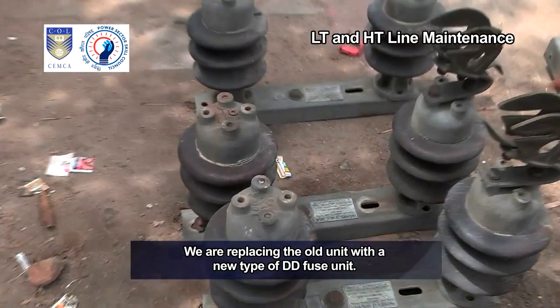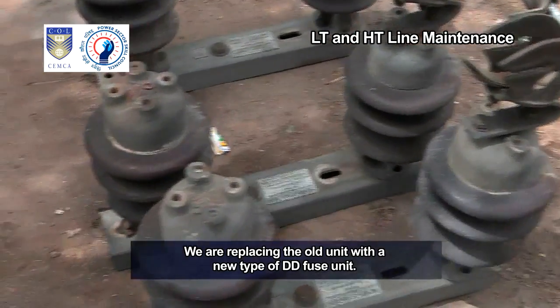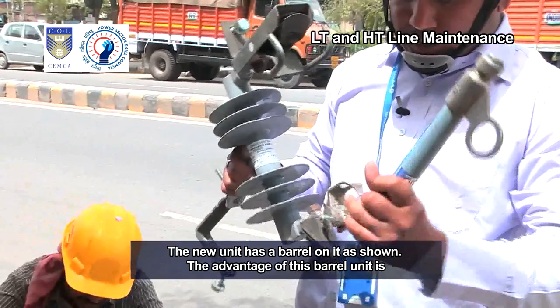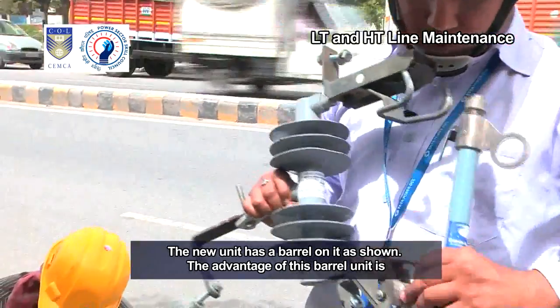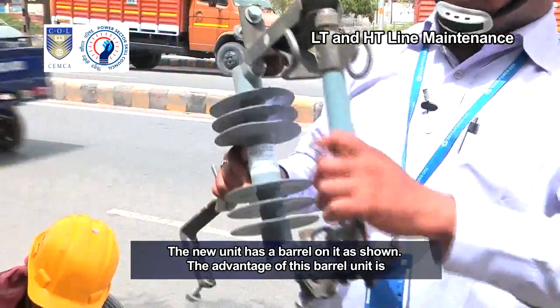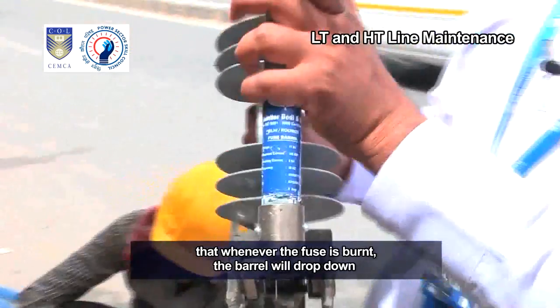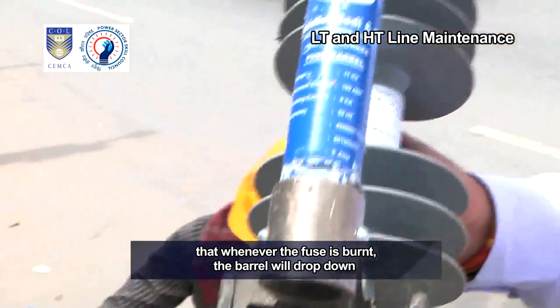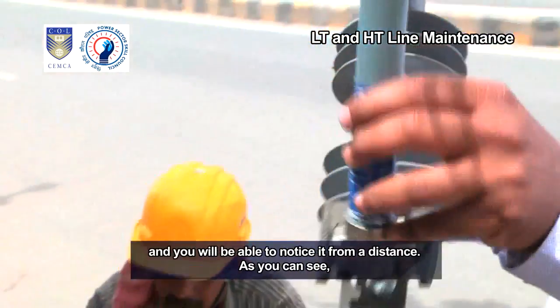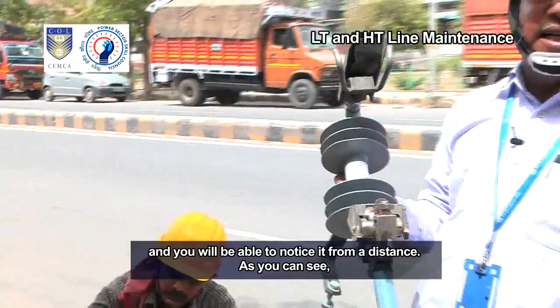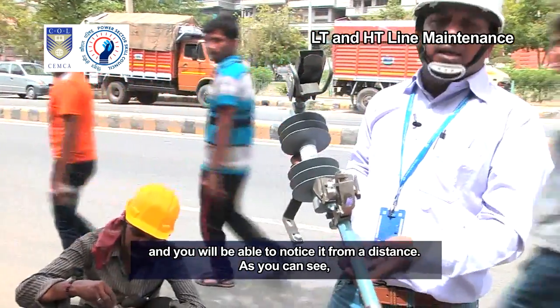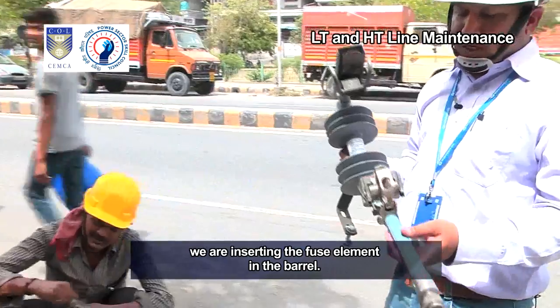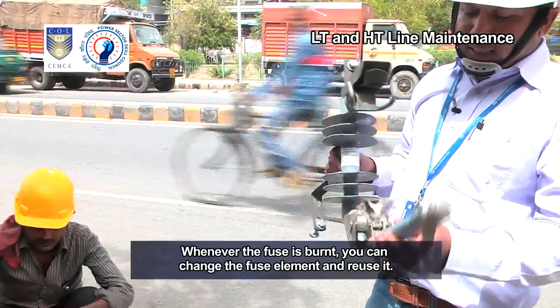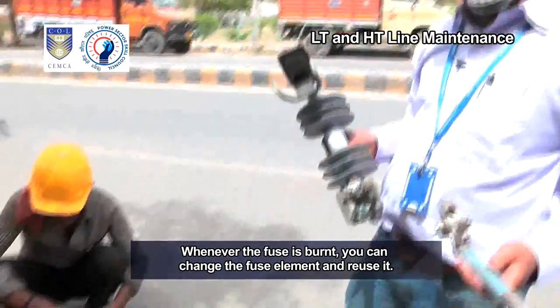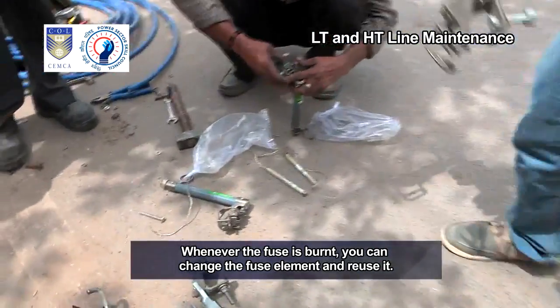We are replacing the old unit with a new type of DD fuse unit. The new unit has a barrel on it as shown. The advantage of this barrel unit is that whenever the fuse is burnt, the barrel will drop down and you will be able to notice it from a distance. As you can see, we are inserting the fuse element in the barrel. Whenever the fuse is burnt, you can change the fuse element and reuse it.